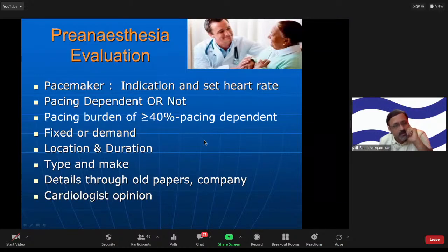Demand mode means the patient intermittently undergoes bradycardia episodes. His normal heart rate may be 70, but it drops to 30 in between. At that time, when the demand arises, if the pacemaker provides that support, we call it demand pacing. The other is fixed mode. The pacemaker won't sense anything. It will go on pacing the heart rhythm at a fixed number, 70 or 80. That we call fixed pacing.